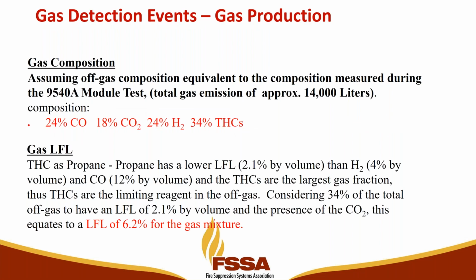So we had an engineering evaluation where we sat back and asked, okay, what does all this stuff mean? This is one scenario that plays out into possibilities. It has to be evaluated for each individual container, off-gas event, UL 9540A, but here's a process that gets you there. We looked at basically 34% hydrocarbons, 24% hydrogen, with a total emission rate, if you look at the failure mode, of over 14,000 liters of gas. We looked at the gas mixture having a lower flammable limit of 6.2% for the mixture.